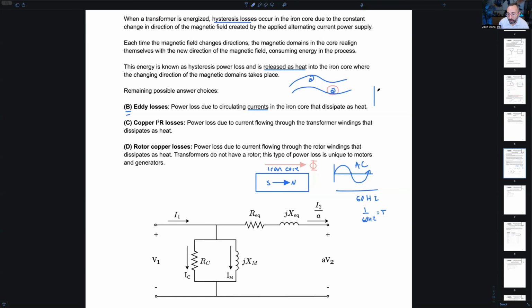So if we talk about those iron core sheets, here's just one individual sheet of iron. When we apply flux, when we induce voltage and current into the secondary winding, we're also inducing a little bit of current circulating in the iron sheets. Those are eddy currents, and the power losses due to the current circulating in the iron laminations are the eddy power losses. They also dissipate, like all power losses, as heat.